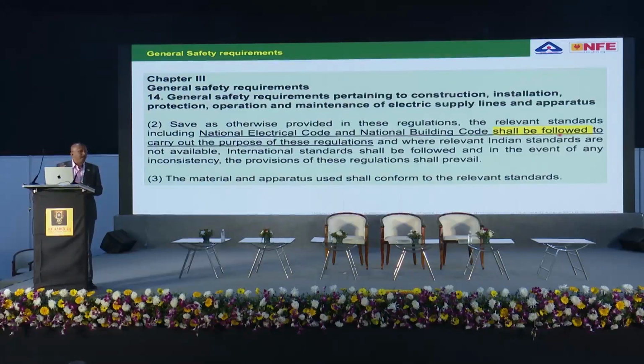National Electrical Code may be followed. May is a recommendation. May means you can follow, if you want to, you follow. Otherwise, still okay. May has been changed to shall, which is going to bring a lot of change. The third one: materials and apparatus used shall conform to the relevant standard. Relevant standard is nothing but the IS standard. If there is no IS standard, IEC standard we should follow. So basically, for the first time after 75 years, the code of practice is made mandatory in the regulation.